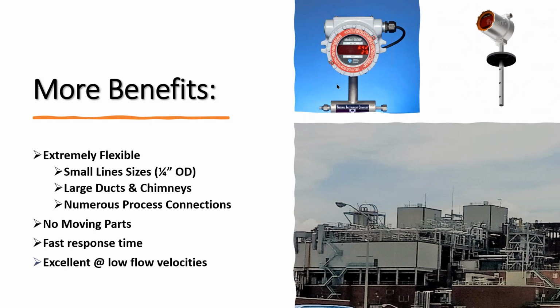There's no moving parts, so you don't ever have to worry about anything really clogging up or jamming. And the response time on thermal mass is pretty good. We're typically about a half second for liquids and about 1 second on gases for the meter to see a change and report that change out. And then we've already talked about some of the low flow velocities where thermal mass, because of that wide turndown, can see at the low end of your flow range as well as at the high end of the flow range. So those are some of the benefits of using thermal mass.